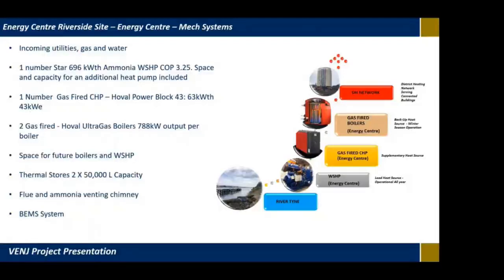We're putting in one gas-fired CHP. It's quite a small unit, 63 kilowatt thermal. Initially we did have a larger unit, but we scaled that back quite considerably to try and run it as flat out as possible. But the plan is to have the heat pump doing the base load and the CHP helping with the shoulder periods, and we've got gas boilers in there as well to do the peak periods in winter. So we've got two gas boilers, 788 kilowatt output per boiler, and two thermal stores, each 50,000 litres capacity.